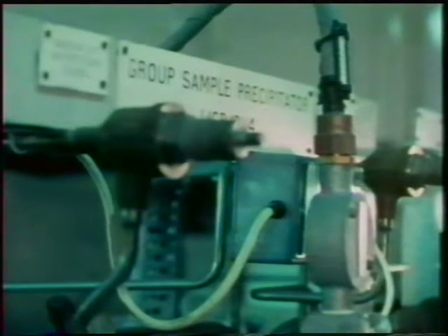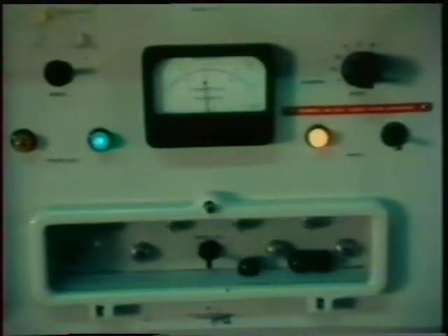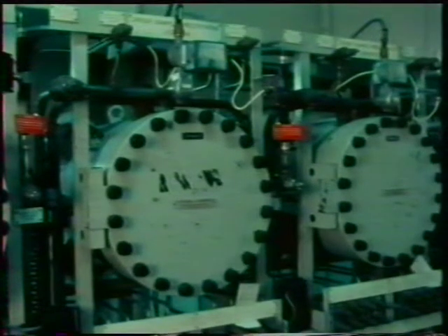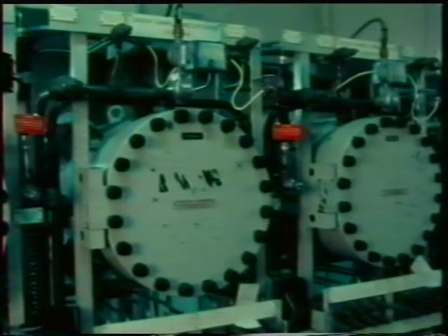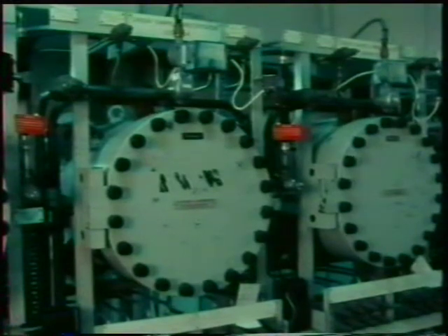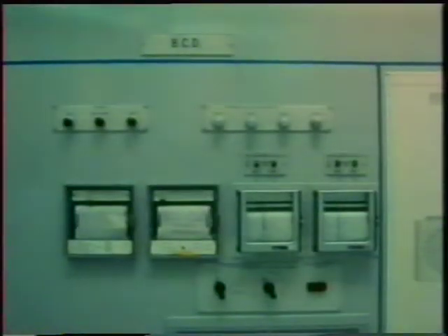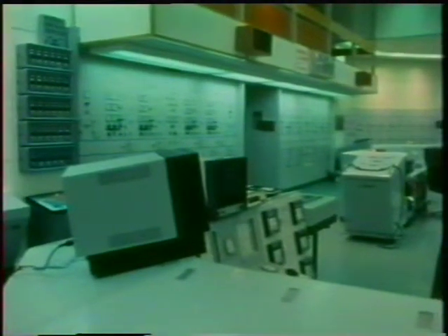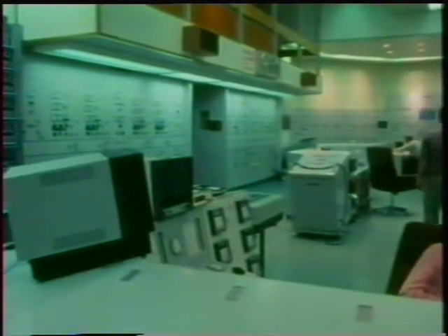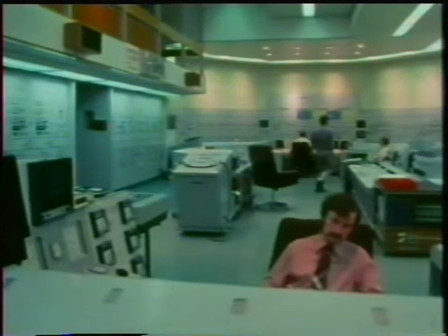If an element should develop a fault and particles of radioactive solid got into the carbon dioxide, a precipitator would collect these solid particles just as if they were ash particles in smoke, and their radioactivity would be detected. This would show that something was wrong in the reactor, and the right steps could be taken to prevent any damage. Instruments in the control room show if the precipitators are picking up any radioactivity. This is just one of the precautions taken in nuclear power plants to make them safe as well as efficient.